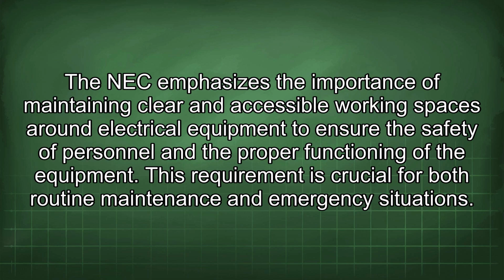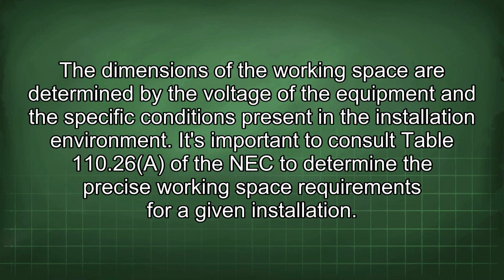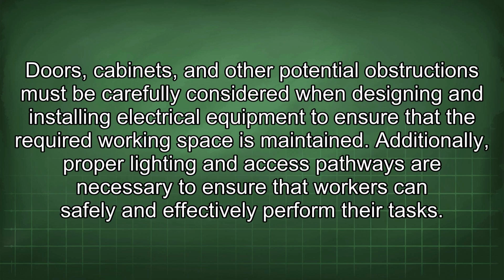This requirement is crucial for both routine maintenance and emergency situations. The dimensions of the working space are determined by the voltage of the equipment and the specific conditions present in the installation environment. It's important to consult Table 110.26 of the NEC to determine the precise working space requirements for a given installation. Doors, cabinets, and other potential obstructions must be carefully considered when designing and installing electrical equipment to ensure that the required working space is maintained.